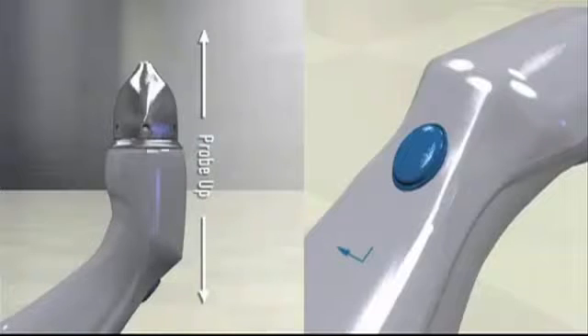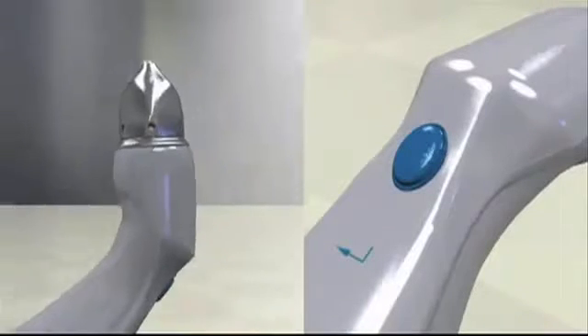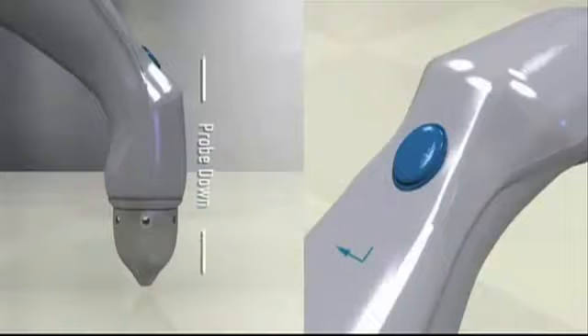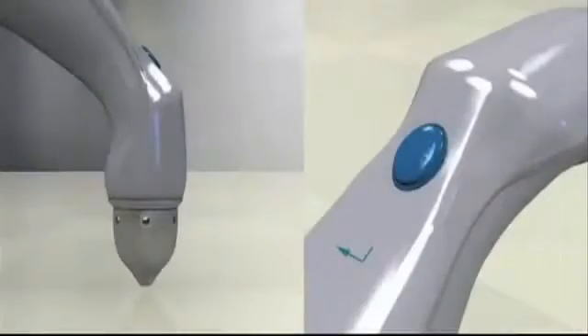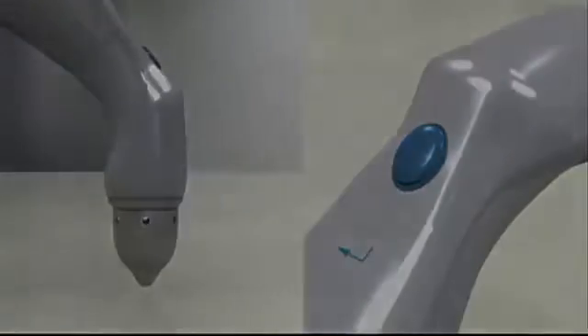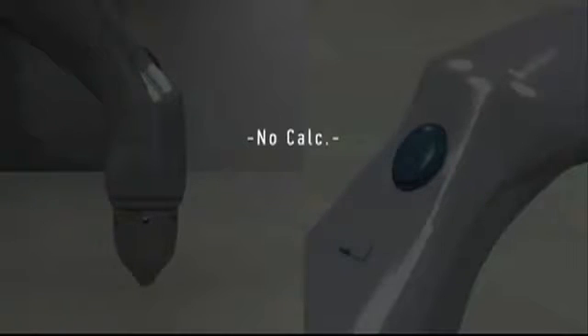The last step in the calibration requires the user to hold the unit so the transducer is pointed directly towards the floor. Press the action button. A calibration number will display on your screen. Consult your user manual to confirm this number is within 30 of the engineered calibration number. When calibration is complete, the unit will feature a number under the probe. If your screen displays a no calc, the calibration process was not performed correctly. Please try to calibrate your unit again. If the unit displays an error message, please consult your AccuPen Vet representative for further support.